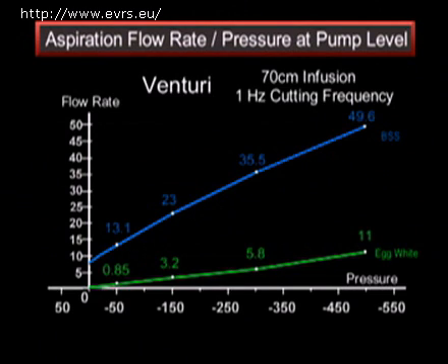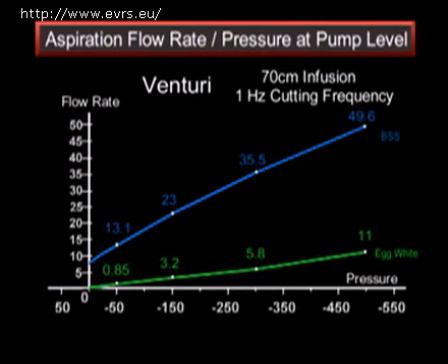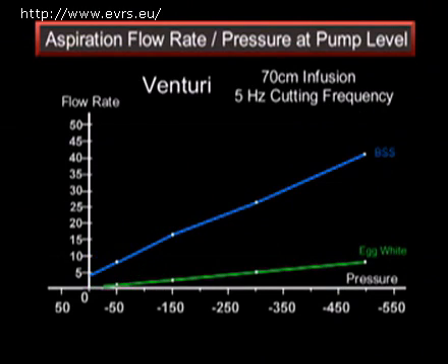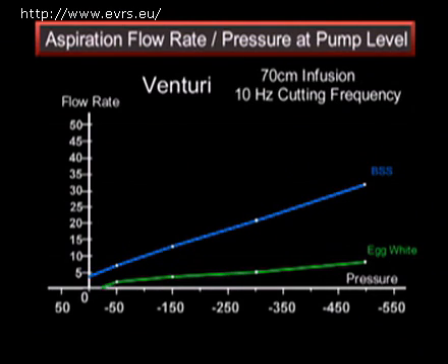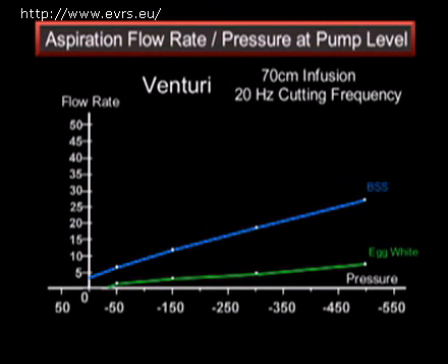Bidet and Colin have confirmed these theories. With a venturi pump at 1 Hz, or 60 cuts a minute, one has 15 times the amount of flow in BSS than in egg white for a depression of minus 50 mmHg, seven times for minus 150, and six times for minus 300. These enormous differences are equally found at 5 Hz (300 cuts a minute), 10 Hz (600 cuts a minute), and 20 Hz (1,200 cuts per minute).